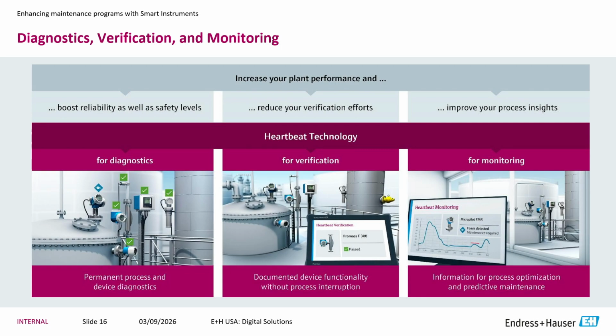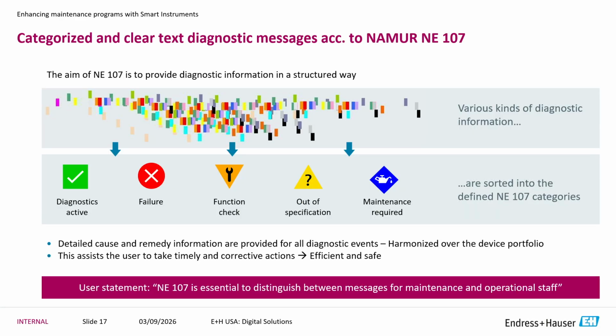Do I have some biofilm forming? Why is this flow tube now heavier than it used to be when I apply the same amount of energy to the excitation system? How you label those inferences is unique to your application. If I was pumping copper slurry, I'm going to start to abrade my flow tube. Now there's less metal in the pipe, so it resonates at a much higher frequency with the same amount of energy. So we can talk about your application in context, and generate thresholds or triggers, or better yet, an extrapolation of what's really happening to my sensor in real time.